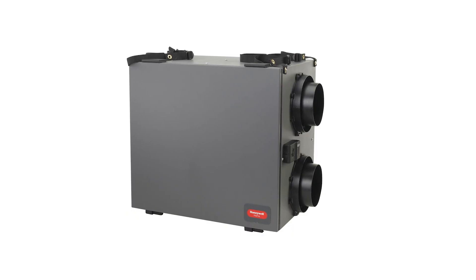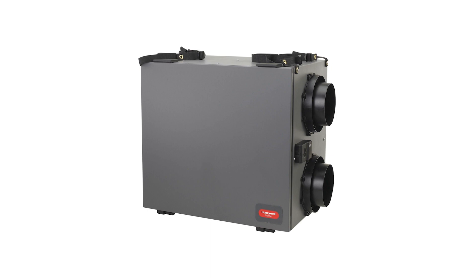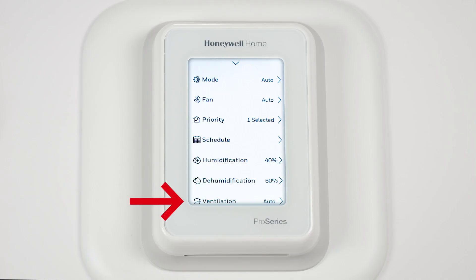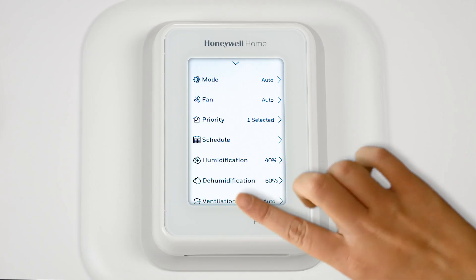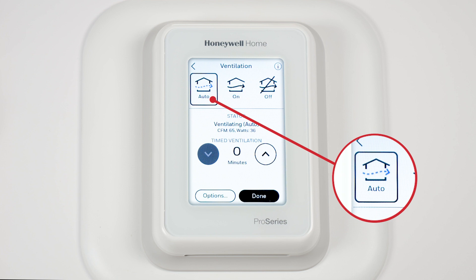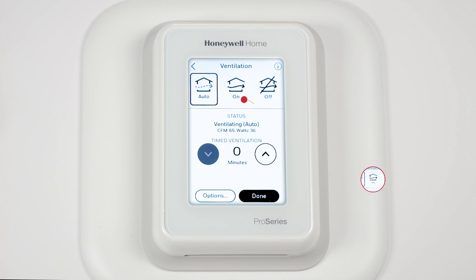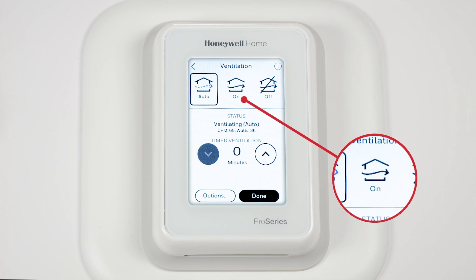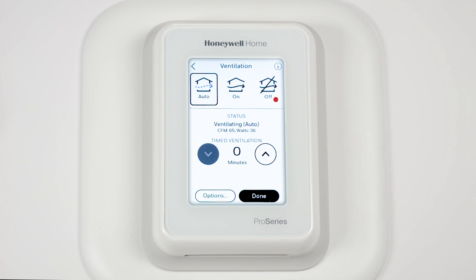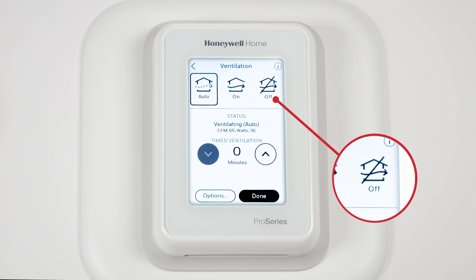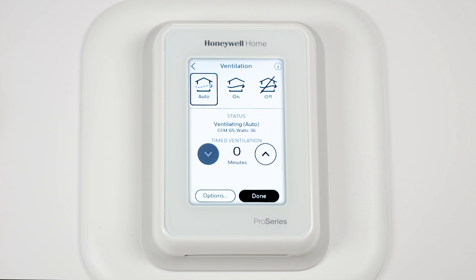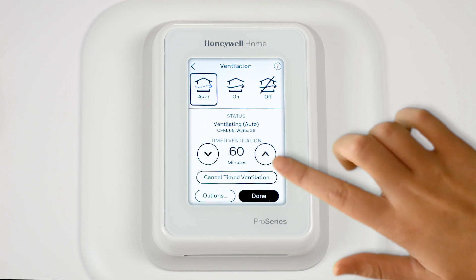Finally, we will look at the ventilator. Select Ventilation. Auto has the ventilation system run as programmed by the installer. On has the ventilation always on. Off has the ventilator off unless manually turned on using the timer. With the timer, turn the ventilator on temporarily up to 180 minutes.